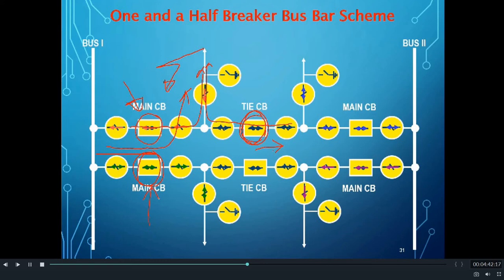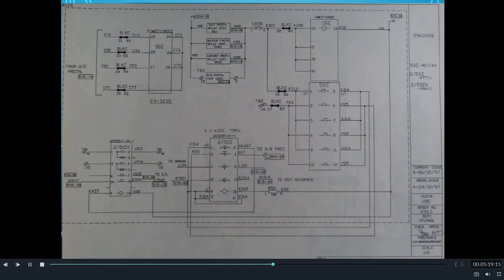Hence, to stop the flow of fault current through the main CB, the main CB of the other feeder will trip. Now we shall consider the second case — non-operation of the TIE CB. During this condition, because of the operation of the main CB, the fault current which was flowing from the main CB side will stop. But the current from the TIE CB side will continue to flow. So, to address that situation, an LBB signal will be generated from the feeder to trip the main CB of the other side feeder. This is how the LBB signals are mapped in the one and a half breaker scheme. This was all about LBB signal mapping in different busbar schemes.